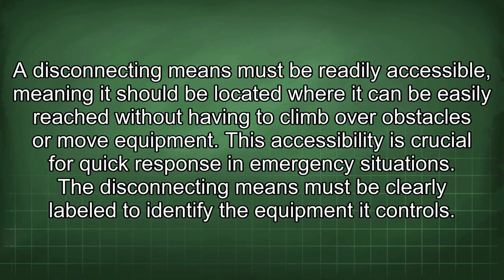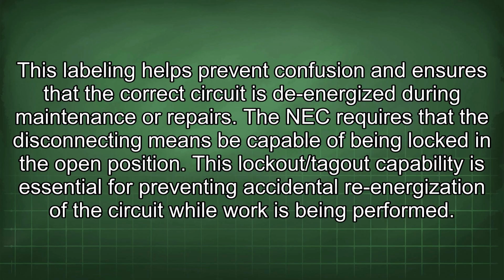A disconnecting means must be readily accessible, meaning it should be located where it can be easily reached without having to climb over obstacles or move equipment. This accessibility is crucial for quick response in emergency situations. The disconnecting means must be clearly labeled to identify the equipment it controls. This labeling helps prevent confusion and ensures that the correct circuit is de-energized during maintenance or repairs.